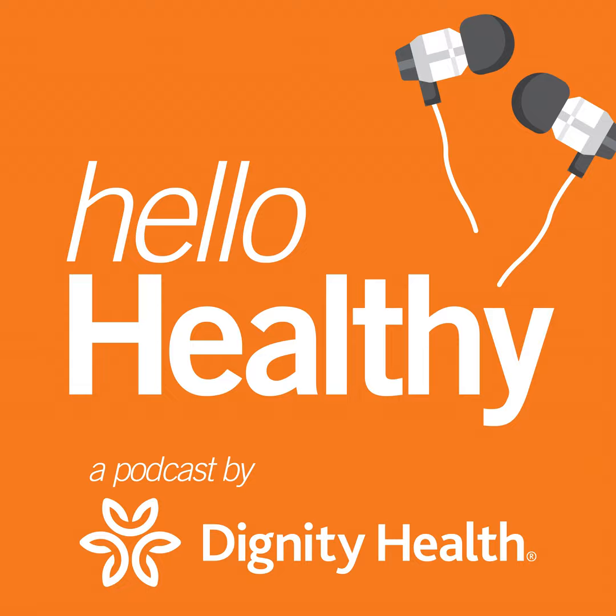Correct. So with devices now, one of the standards of care is that we're able to monitor these pacemakers remotely. So most patients, when they get a device implanted, go home with a little monitor that sits next to their bed. And at night, the pacemaker will communicate with this monitor if it's having any issues. The pacemaker is not working properly. There's issues with the patient's own heart. If they're going into some sort of arrhythmia that the device is alerted to look for, it will actually send us here at the clinic a report.